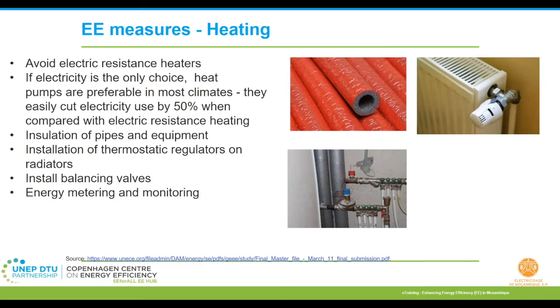So I would avoid using electrical resistance heaters. But if you do not have any other options, and you have only electricity as a choice, then if your climate or weather conditions favor, you can opt for heat pumps rather, which should actually cut down your electricity use by almost 50%. Then yes, insulation of pipelines and equipment is required. Thermostatic regulators can also be used if you have radiators in place.